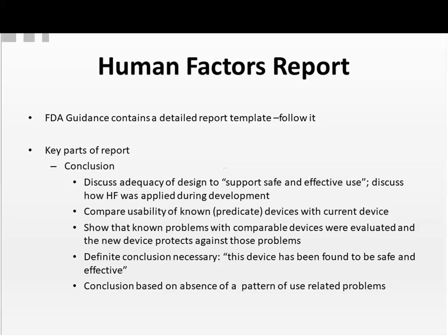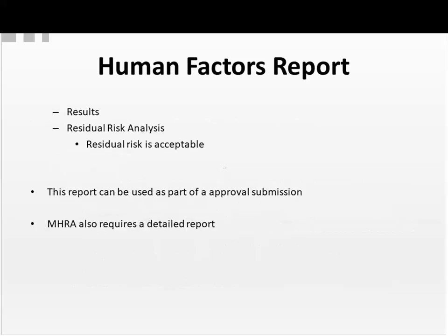You must be able to reach a definite conclusion that the device has been found to be safe and effective, and back that up with data. Your report will have a results section and a residual risk analysis, and where your conclusion is that the residual risk is acceptable.